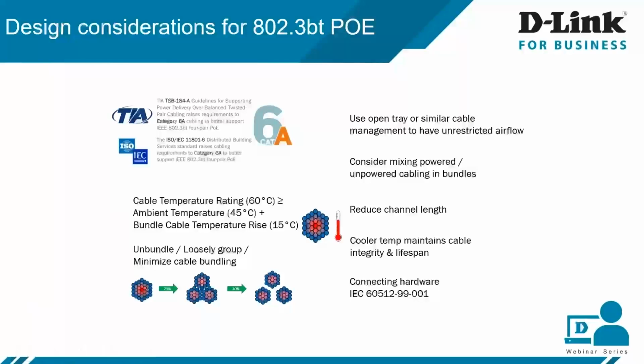Somebody can ask, what points do we need to consider if we are using Type 3 or Type 4 PoE? The new type of Power over Ethernet is also commonly referred to as PoE++ or 4-pair PoE, which supports more power. Due to high power, there will be significant heat rise and cable arcing, which could have a harmful effect on the cabling system performance. An extreme temperature which can exceed the cable operating range can damage the cable.